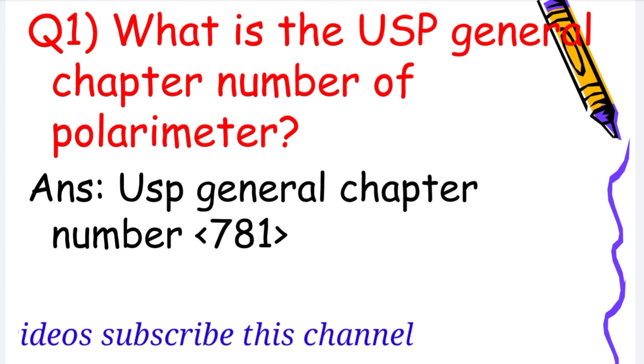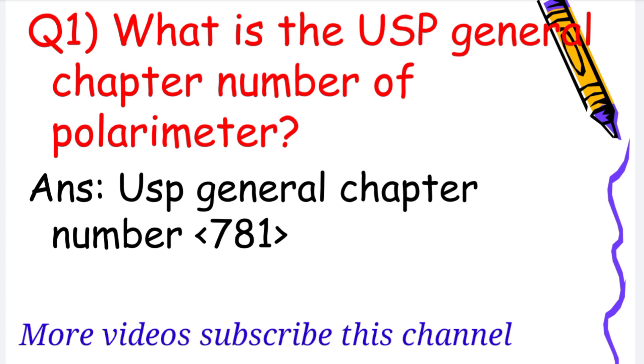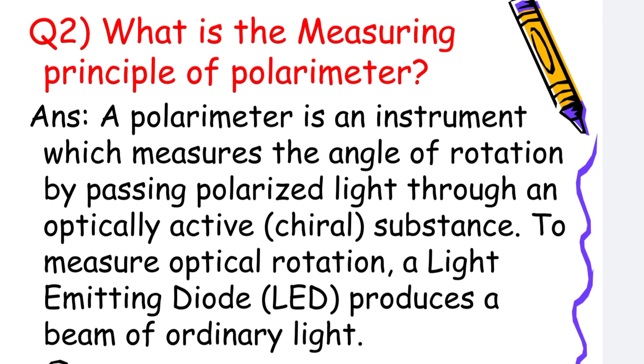Question number 1 is: what is the USP general chapter number of polarimeter? The answer is USP general chapter number 781. Next: what is the measuring principle of polarimeter? A polarimeter is an instrument which measures the angle of rotation by passing polarized light through an optically active substance.